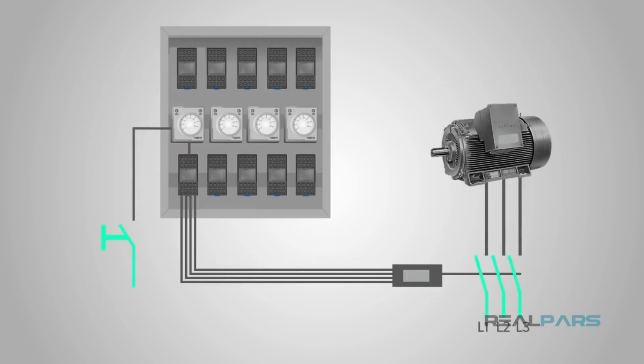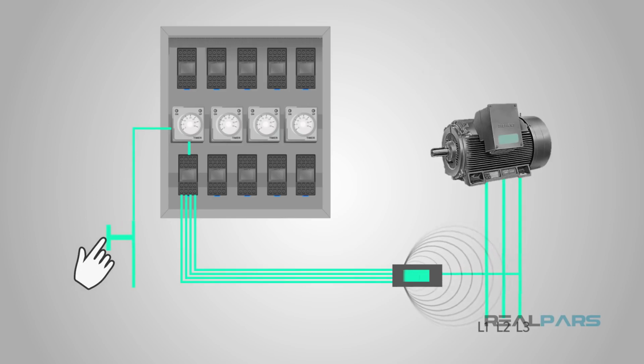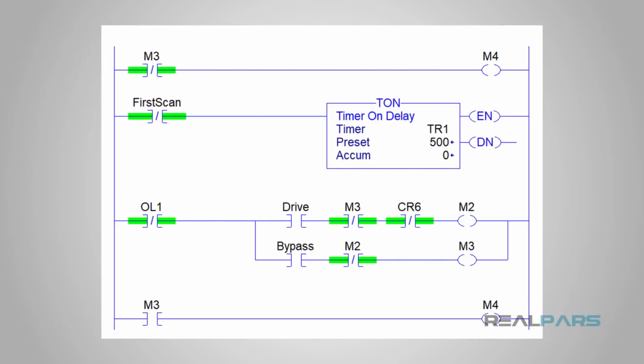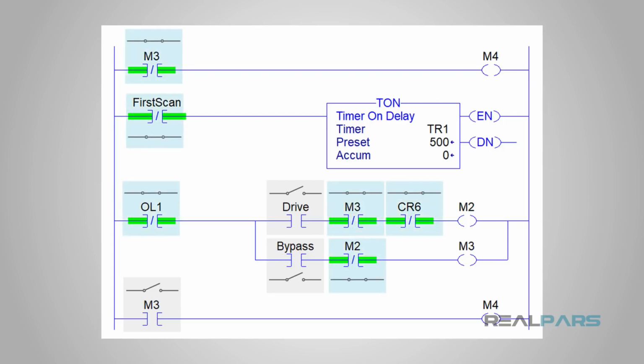Relays are simple devices, consisting of coils and the contacts that they move. When electricity energizes the coil, it moves the contacts, connecting some and disconnecting others. The lowest level elements of ladder logic mimic those relay functions. Here is an example of the logic from the example drawing I've been using, rendered in Rockwell Software's Studio 5000.